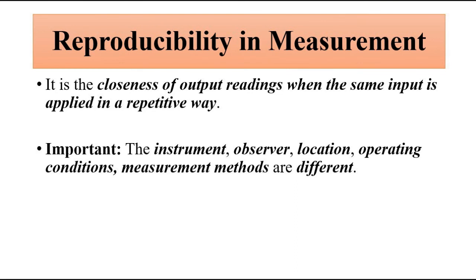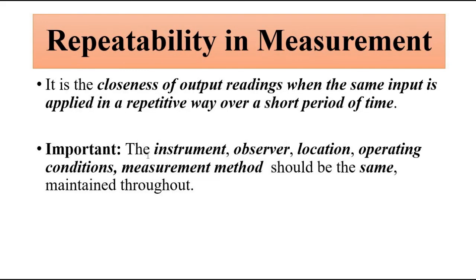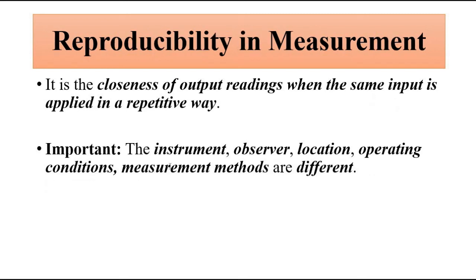So in summary, repeatability and reproducibility both mean closeness of multiple output readings when a particular fixed input is applied to a system. But in repeatability, the same instrument, method, observer, location, and operating conditions are used. In reproducibility, different instruments, methods, observers, locations, and operating conditions are used. That is what separates repeatability from reproducibility. This is an important concept related to the measurement system.